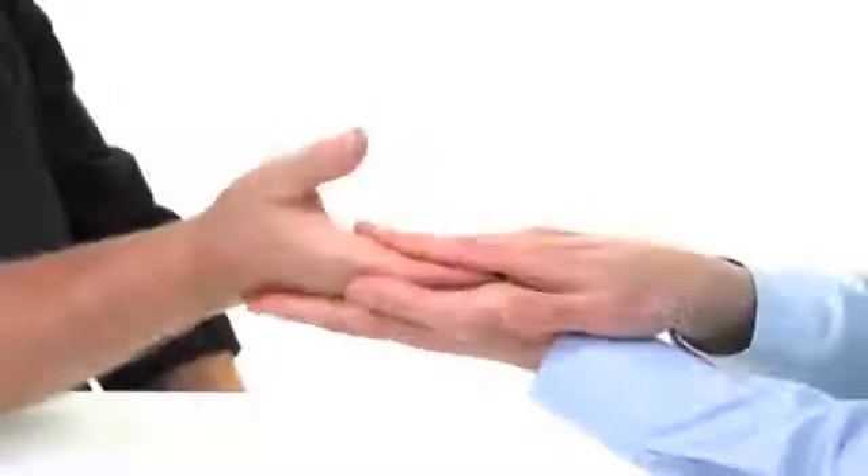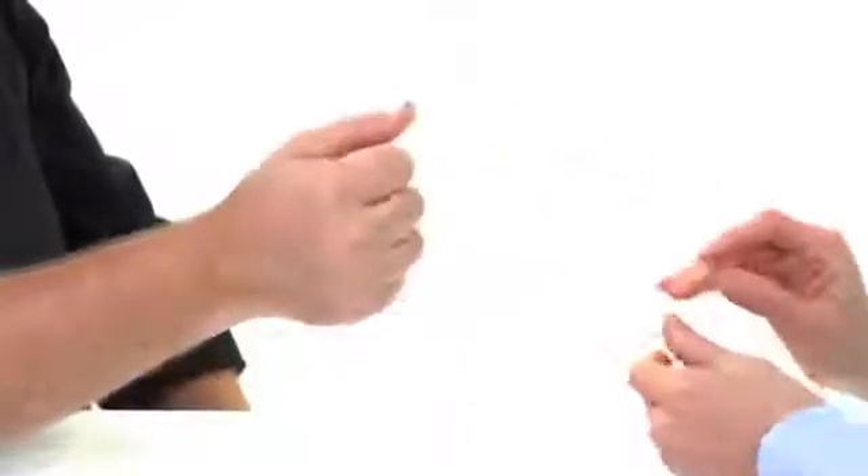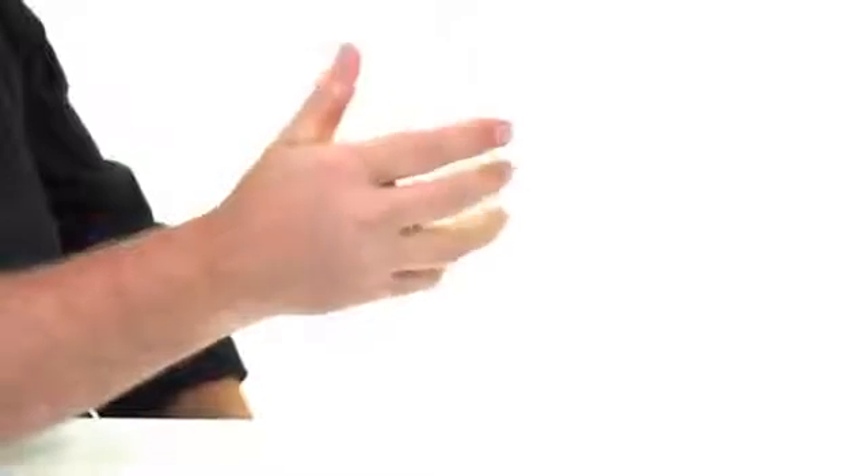You can silence and restore the alarm with the press of the on-off button. Check and correct the position of the sensor if it has moved, and recheck the sensor connection to the oximeter. If the hand has been grasping a rail or other object, or it is cold, relax and warm the hand to restore stronger blood flow.